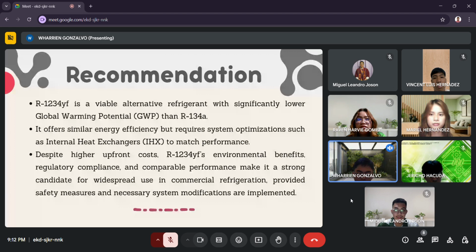Next, we have the recommendation. R1234yf is a viable alternative refrigerant with significantly lower global warming potential, or GWP, than R134a. Second, it offers similar energy efficiency but requires system optimizations such as internal heat exchangers, or IHX, to match performance. Third, despite higher upfront costs, R1234yf's environmental benefits, regulatory compliance, and comparable performance make it a strong candidate for widespread use in commercial refrigeration, provided safety measures and necessary system modifications are implemented.